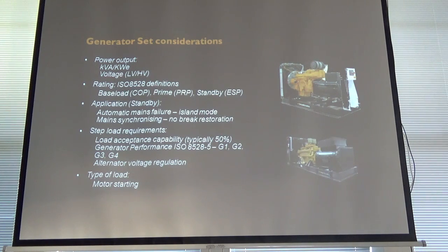One of the other key things that comes into play is its load acceptance capability. Typically, of the high-end generators we can supply, the Mitsubishi, the Perkins, the MTU, the Cummins, they'll all take a cold load acceptance of about 50% of its rating. So say this unit, a prime rating which is 1 MVA, it'll take a 500 kVA load step. Okay? Some units will take 100% load step and not stall.